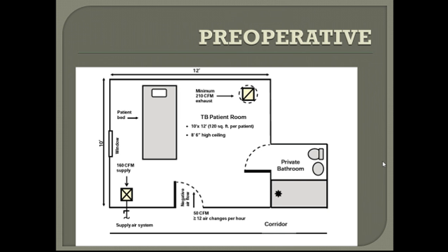As I said, now we have to know where to place this patient pre-operatively. We have to place this patient in a place that protects others from getting infection from him. It is what's called a negative pressure isolation room. As you see here, this room has a private bed, a single patient room, a private bathroom, an air supply of 160 CFM and an exhaust of 210 CFM, which causes negative pressure in this room.